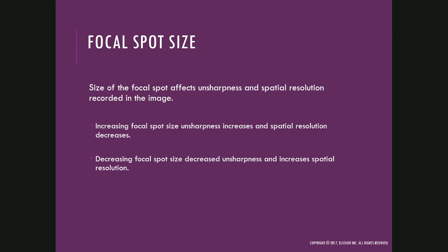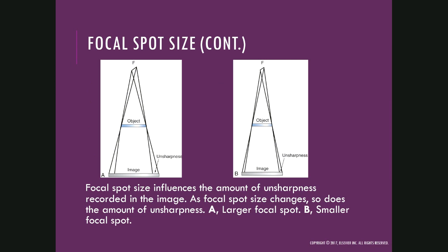If you have a larger focal spot size, it's better for heat dissipation and spreading out that exposure over more area on the anode. But it does come at a cost, and that cost is decreased spatial resolution. That can be demonstrated here on slide number 18.